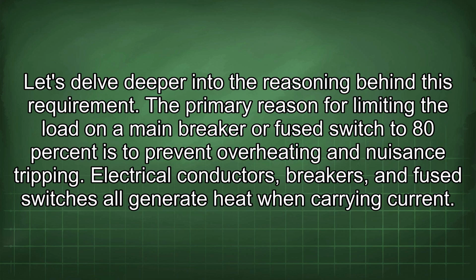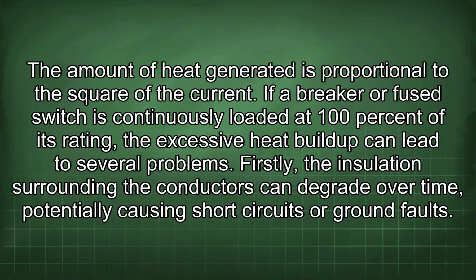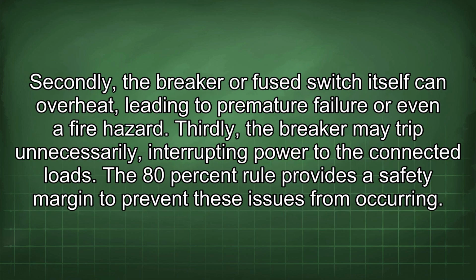The primary reason for limiting the load on a main breaker or fuse switch to 80% is to prevent overheating and nuisance tripping. Electrical conductors, breakers, and fuse switches all generate heat when carrying current. The amount of heat generated is proportional to the square of the current. If a breaker or fuse switch is continuously loaded at 100% of its rating, the excessive heat buildup can lead to several problems. Firstly, the insulation surrounding the conductors can degrade over time, potentially causing short circuits or ground faults. Secondly, the breaker or fuse switch itself can overheat, leading to premature failure or even a fire hazard. Thirdly, the breaker may trip unnecessarily, interrupting power to the connected loads.